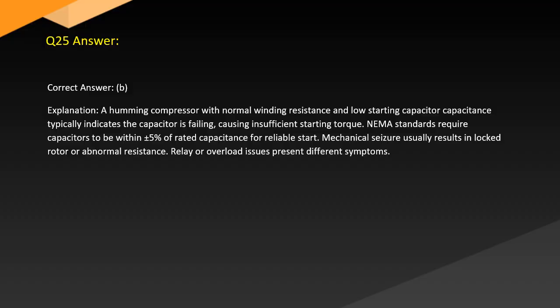Answer. Correct answer: B. Explanation. A humming compressor with normal winding resistance and low starting capacitor capacitance typically indicates the capacitor is failing, causing insufficient starting torque. NEMA standards require capacitors to be within plus or minus 5% of rated capacitance for reliable start. Mechanical seizure usually results in locked rotor or abnormal resistance. Relay or overload issues present different symptoms.